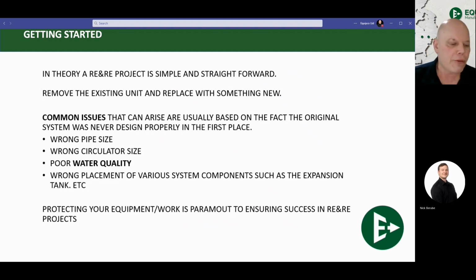For example, if you have a 100,000 BTU boiler and you try to pipe that boiler with half-inch pipe, I don't care if it's PEX or copper, anything that small, there's no way you're going to carry 100,000 BTUs through pipe that size without moving it through that piping at the speed of light. So piping needs to be sized properly for the BTUs that you are moving. We get that one all the time. There's beautiful charts online. There's apps you can use to make sure you get the pipe sized right.